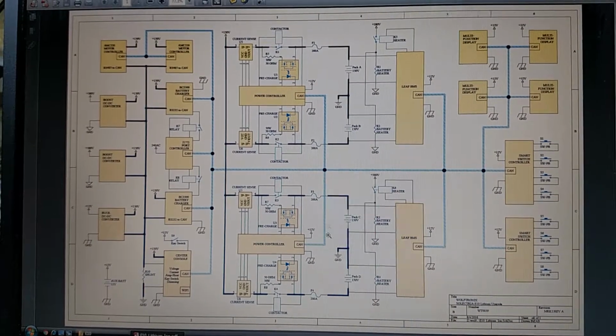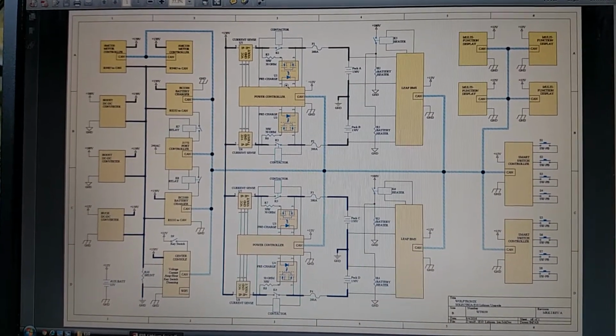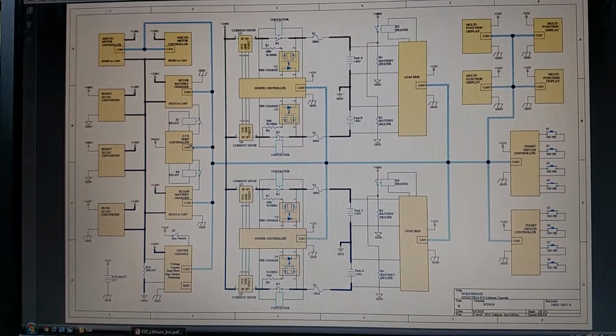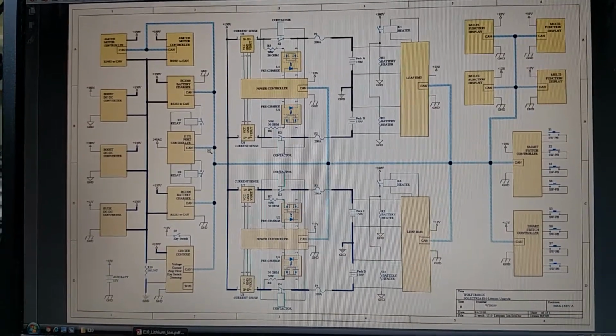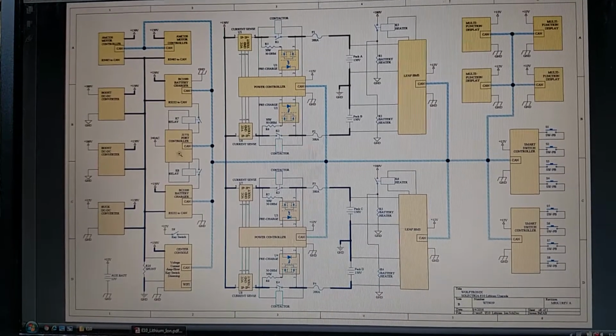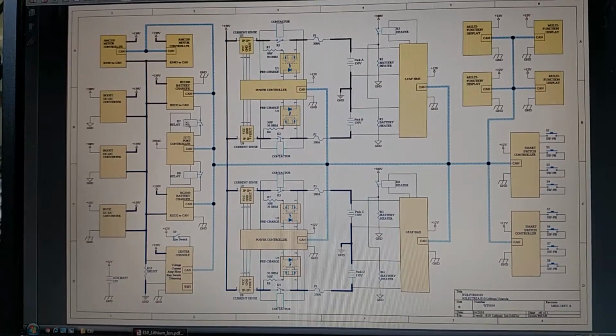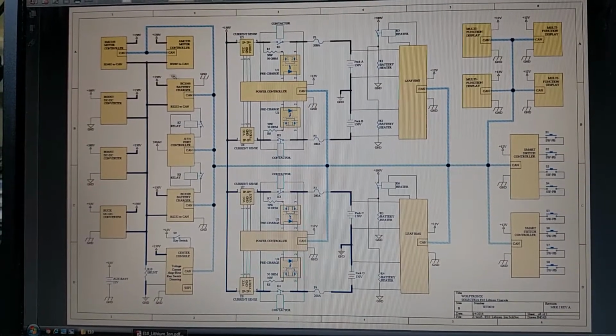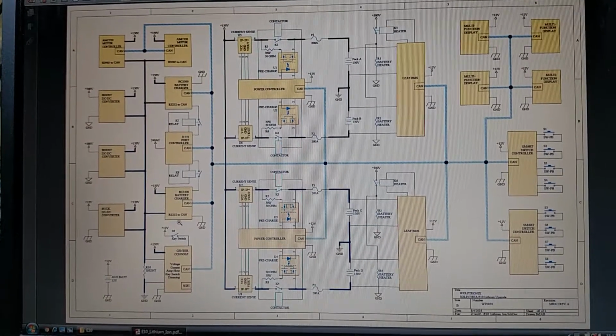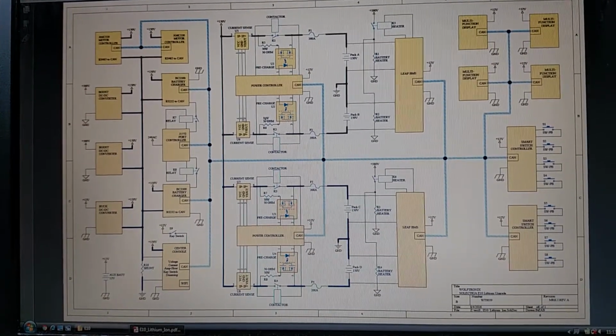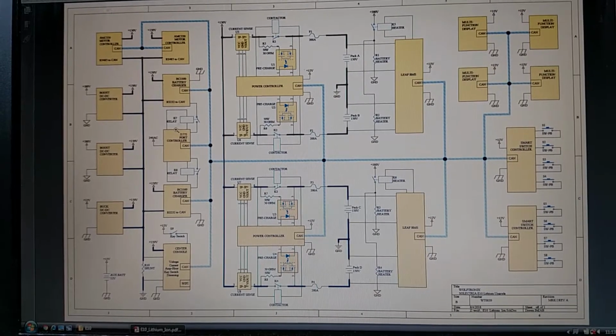So we can disconnect the packs. But if for some reason that wasn't working, then we can go tell the charging station to shut down. And if for some reason that doesn't work, we can always open up the contactor, which provides AC to the battery chargers, and kick them out of the loop too. So there's 3 levels of safety. I think that's going to be pretty good.